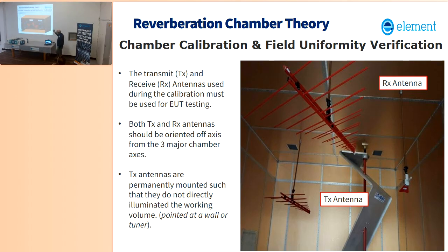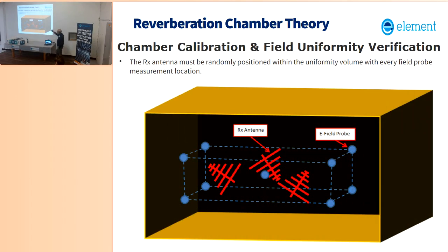So when you do the field uniformity verification and the calibration, you've got to have the antennas in there and you've got to have the probes in there. And you're continuously moving the antenna around, moving the probe from one location to the other, all 9 different locations. So you end up with lots and lots of calibration data in this process, as opposed to the anechoic chamber method where you end up with 1.